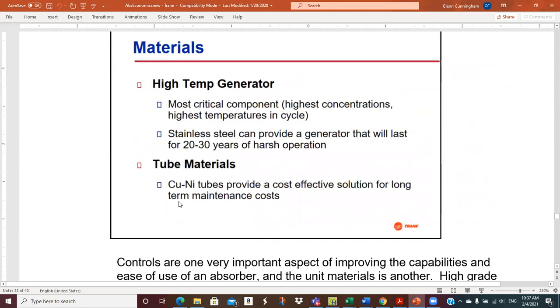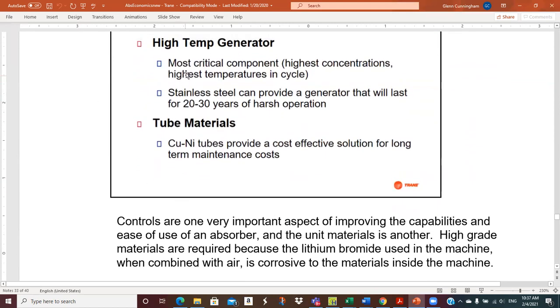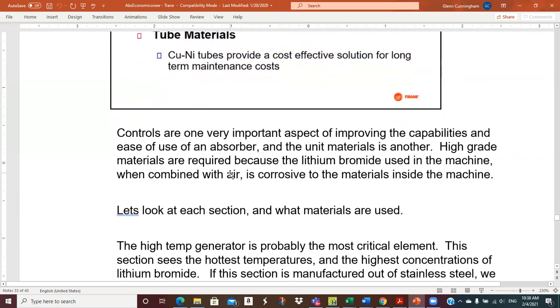Generator has to do with materials. So the most critical component, it sees the most aggressive service because it's got the strong solution of lithium bromide at the highest temperature. So that's going to be the most corrosive environment. And so by going to stainless steel, they can create a generator that will last 20 to 30 years, which is probably the lifetime of the machine. So that's pretty good. And then some of the other areas, we can go to copper nickel tubes, which provide a cost-effective solution for maintenance. So that's all corrosion.